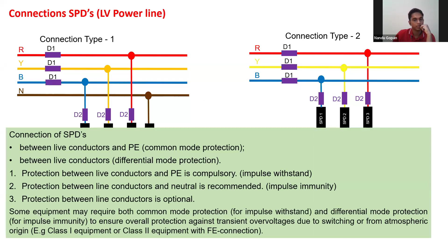So this is a few things which I will ignore. So how does an SPD work in a current GPR? You have a 3+1 connection system. R Y B is connected to neutral, and between neutral and PE there is one SPD. This is a 3+1 connection type 2.